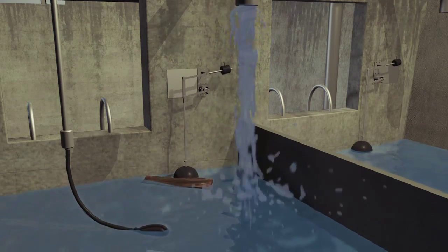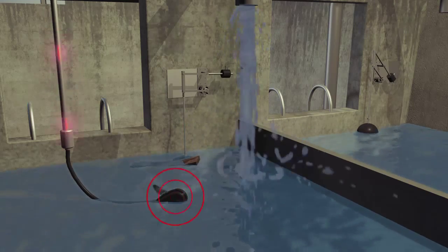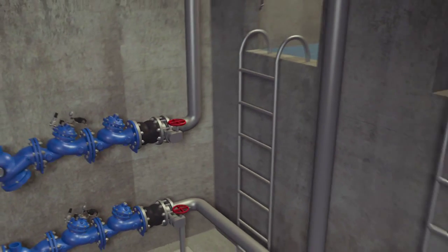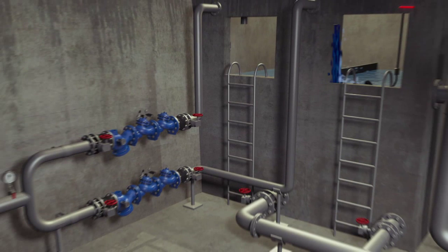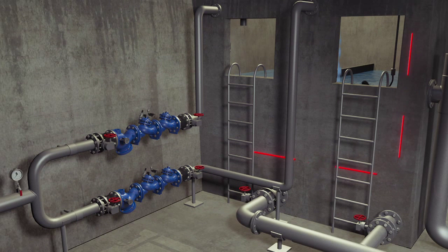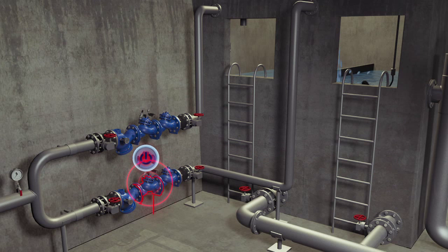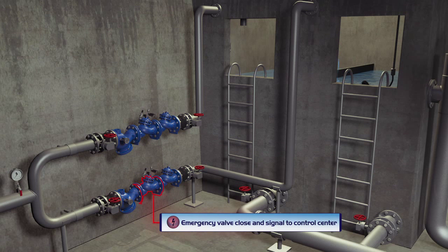When water reaches the emergency level, the electric float is activated and terminates filling by closing the safety valve. At the same time, the safety valve sends an alarm signal to the building's engineer control system or to a central control system.